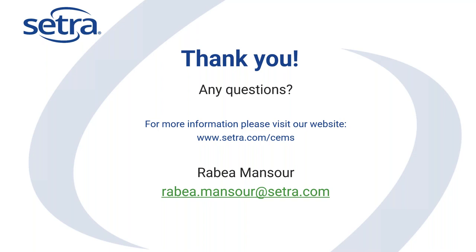There's a note asking if it's possible to send the presentation. If you're looking for a copy of the presentation beyond the webinar recording, reach out to Rabea or through one of our contact forms and we can send it to you individually. Next question: can we do zero calibration with the cover installed? Yes — best practice is to do this when the room is not in use. You'd open all the doors or barriers across the hallway, anteroom, and protected space so that pressure is at equilibrium across all the monitored area. Then you truly have ensured a zero pressure differential across the space. To access the menu of the Setra Light and adjust, you just snap the front cover off, go through the menu to get to the zero check, and put the cover back on.